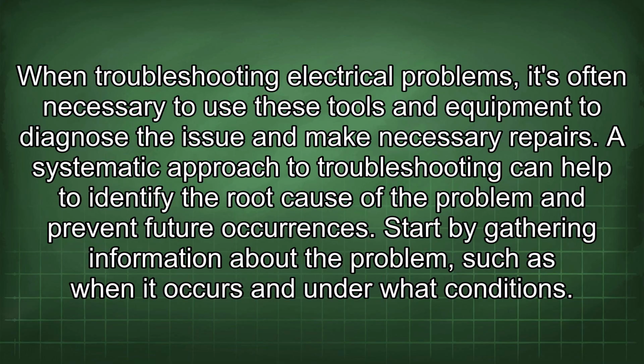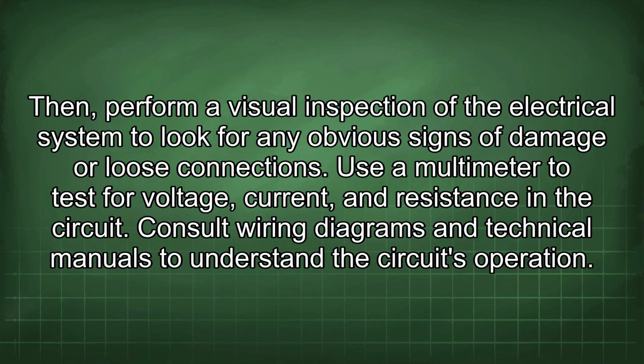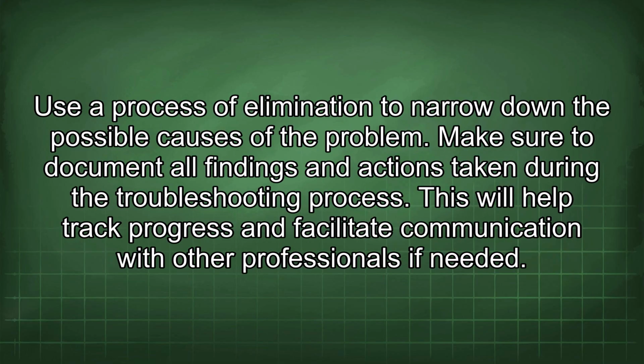Start by gathering information about the problem, such as when it occurs and under what conditions. Then perform a visual inspection of the electrical system to look for any obvious signs of damage or loose connections. Use a multimeter to test for voltage, current, and resistance in the circuit. Consult wiring diagrams and technical manuals to understand the circuit's operation. Use a process of elimination to narrow down the possible causes of the problem.